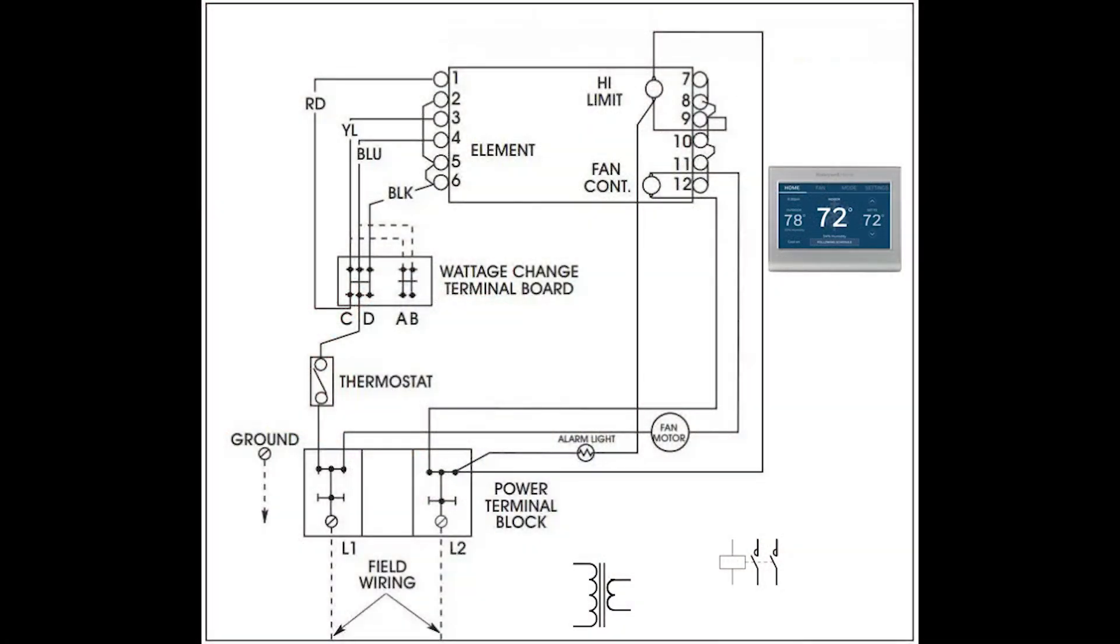First things first, remove the original thermostat from the circuit. Next, we'll wire in the transformer, primary side to the field wiring lugs. One of the 24 volts secondary lines will go directly to one side of the coil in the contactor. The other side of the 24 volts will connect directly to the R terminal of the new thermostat.